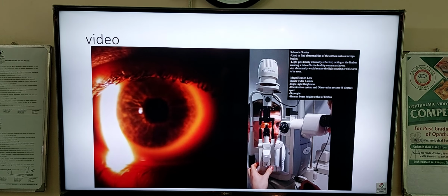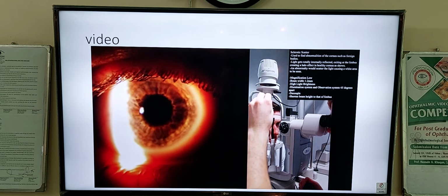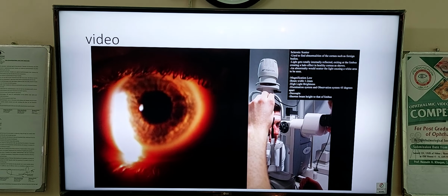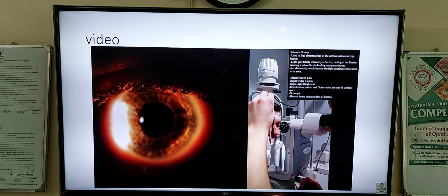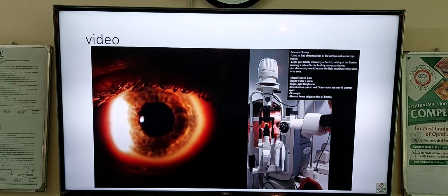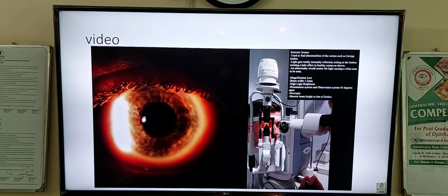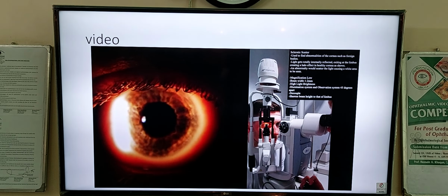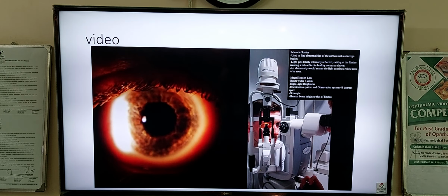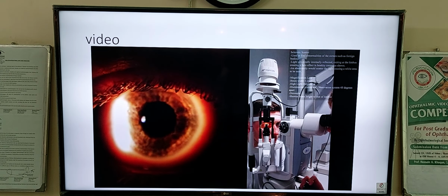Then shorten the beam height so that all the light is in contact with the limbus, as extra light can be scattered by the sclera, reducing visibility. The light is totally internally reflected in a healthy cornea and exits at the limbus, creating a halo effect, which can be seen here. If the cornea would have any abnormalities, they would scatter the light, causing a white area to be seen at its location.